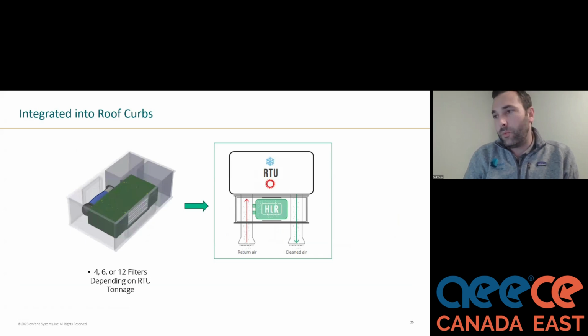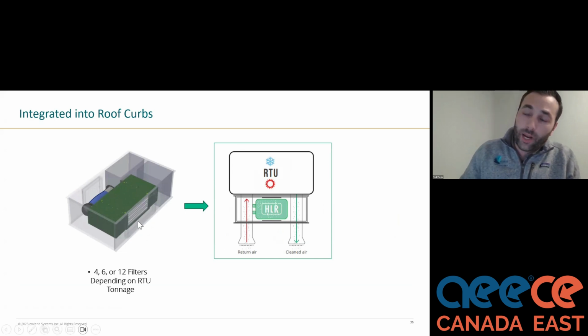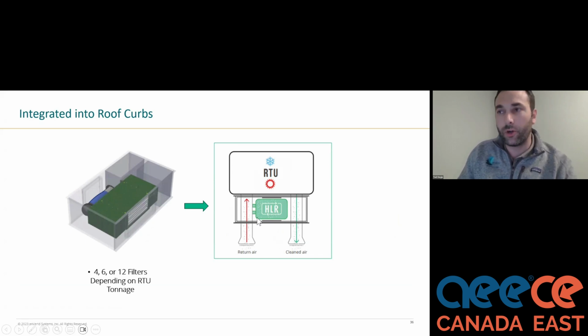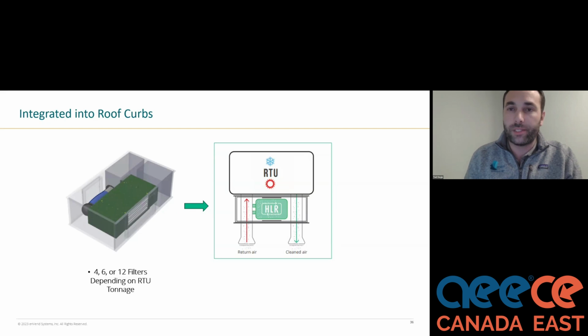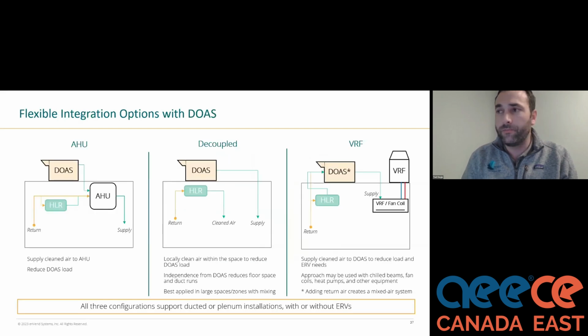Here's an example of what these filters would look like integrated into a curb. You can select a variety of sizes here, variety of number of filters, which would impact the amount of air cleaning done in that calculation. This unit here would have a fan off to the back, and basically you have the RTU up above this curb. HLR stands for HVAC load reduction. That's kind of an abbreviation for systems that are able to scrub contaminants of concern coming out of return air and reduce the amount of outside air that needs to be brought into that RTU.